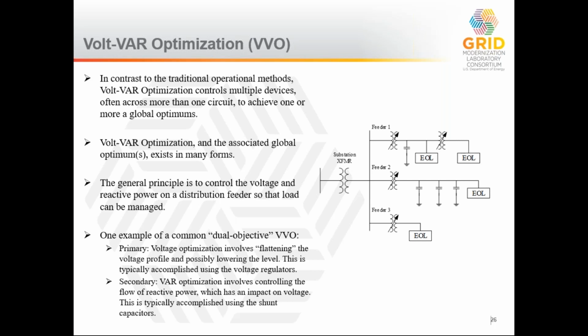What it does is flatten the voltage profile across the entire distribution circuit, pushing it down to the low end of the acceptable band. This reduces the overall energy consumption, making the system operate more efficiently. It's been well shown that if you operate on the low end of that band, loads will still provide the same quality of service, they just operate more efficiently.